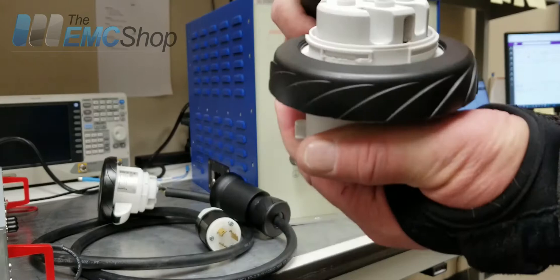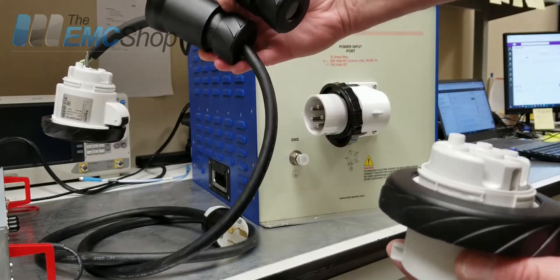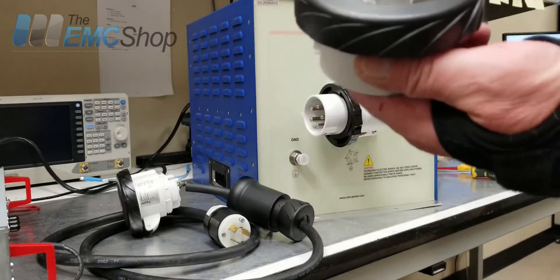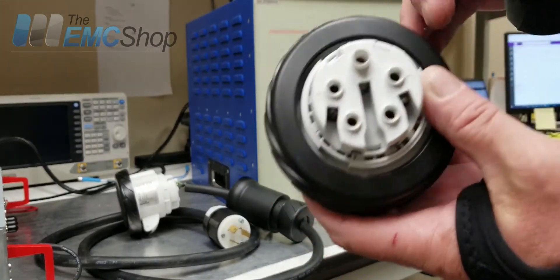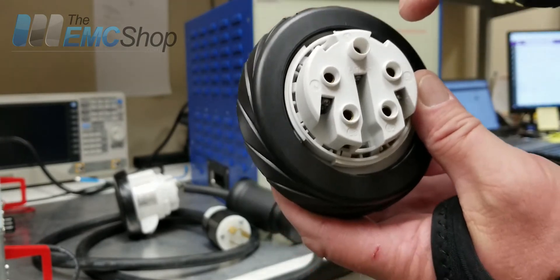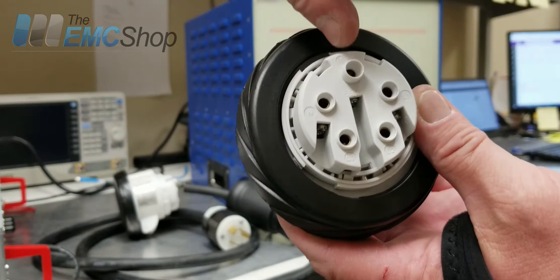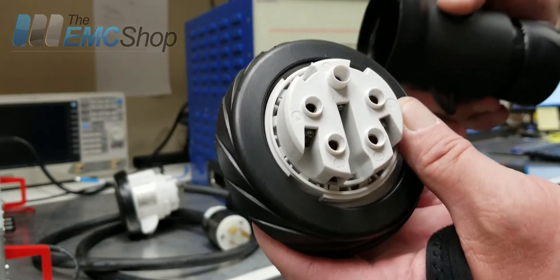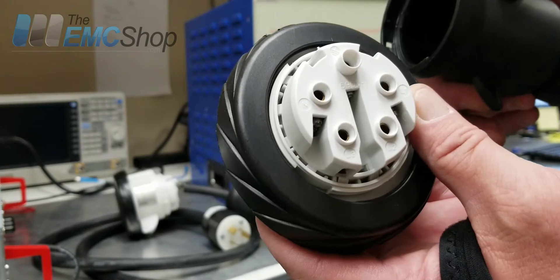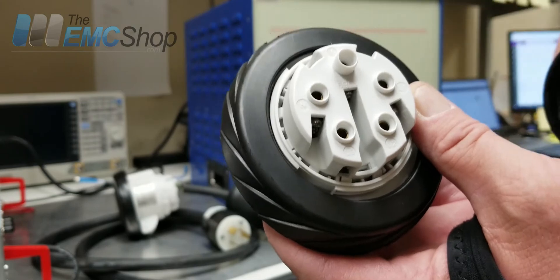Each connector comes in two parts that hold your cable leading up to the connector. Inside the connector you'll have five pins: L1, L2, L3, neutral, and ground. All of these are labeled, so you just make sure you plug into the ones you're going to be using. You could use all five, or two, three, or four, depending on what application you need it for.